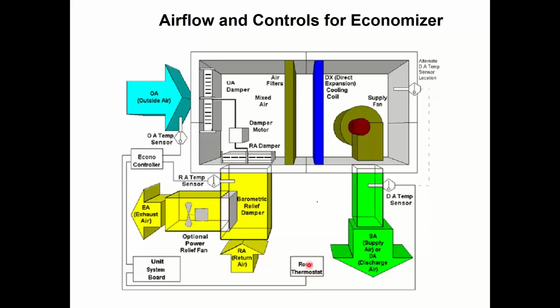So the thermostat asks for the compressor to come on, or it asks for cooling. The economizer gets first dibs on that. And if it says, no, it's not nice out, it's too hot out, or it's too humid out, don't do it, then we go ahead and run the compressor like a normal system. But if it is cool out, then we don't run the compressor. And instead what we do is we start modulating this outside air damper to provide me cool air.